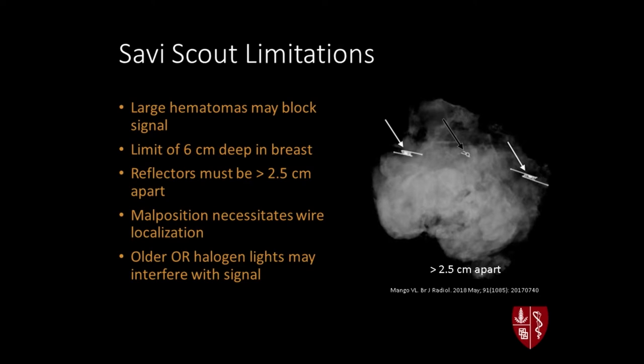The Savi Scout reflector can be placed up to 6 centimeters deep in the breast, beyond which the signal may be difficult to detect. If targeting multiple targets or bracketing a very large target, the individual reflectors must be greater than 2.5 centimeters apart, or the overlapping signal may make the individual reflectors difficult to find.